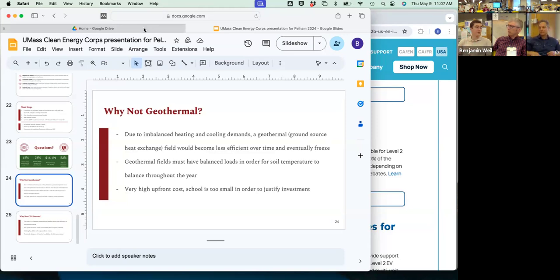And as we saw in the efficiency graphs, there's a lot of times where, at a certain air temperature, air source is actually more efficient than geothermal, because geothermal has a constant ground temperature. If you're only heating the air by, say, 10 degrees, you actually have a higher coefficient of performance than you would with the geothermal system. So it just didn't make a lot of sense to us. The main one really is the thermal imbalance. Yeah, that makes a lot of sense.